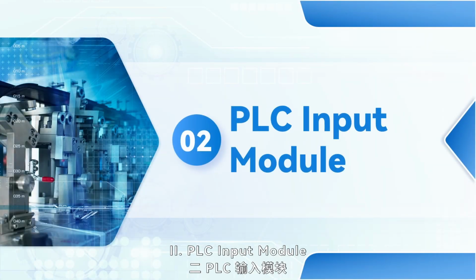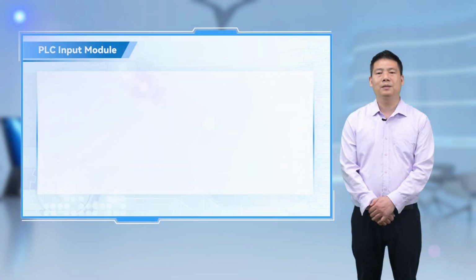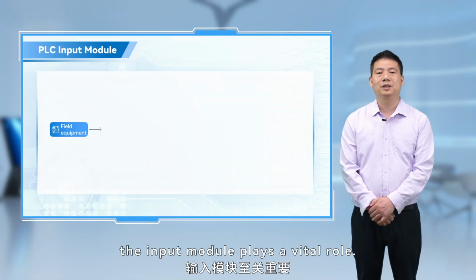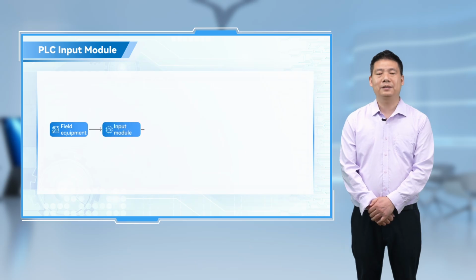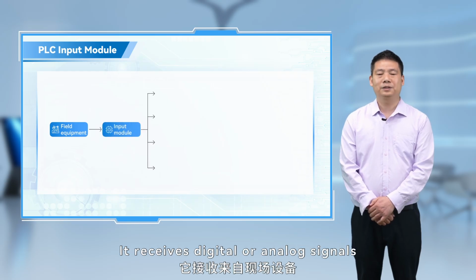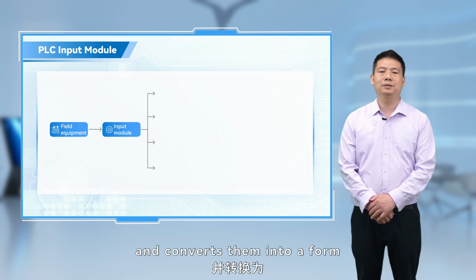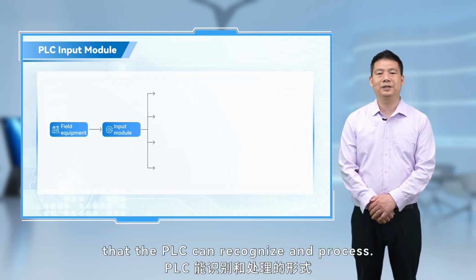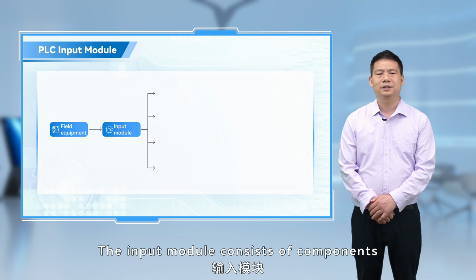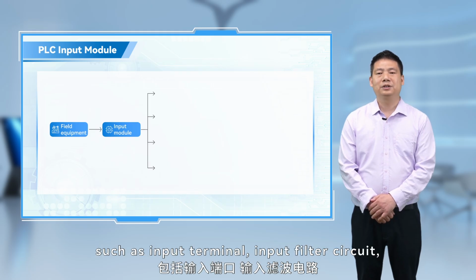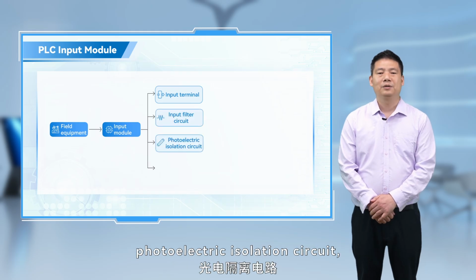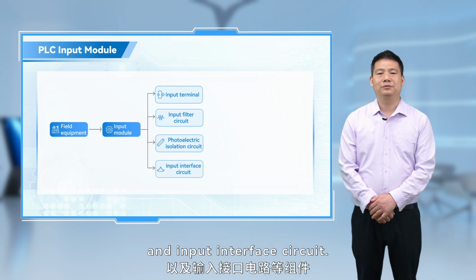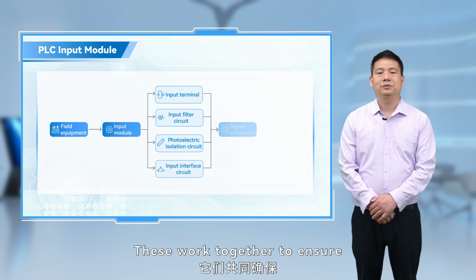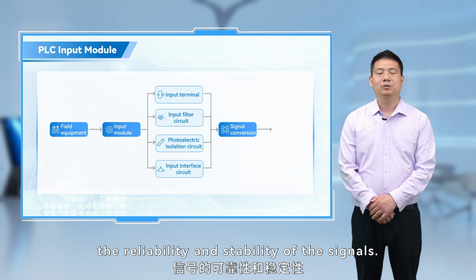2. PLC Input Module. In a PLC control system, the input module plays a vital role. It receives digital or analog signals from field devices and converts them into a form that the PLC can recognize and process. The input module consists of components such as input terminal, input filter circuit, photoelectric isolation circuit, and input interface circuit. These work together to ensure the reliability and stability of the signals.